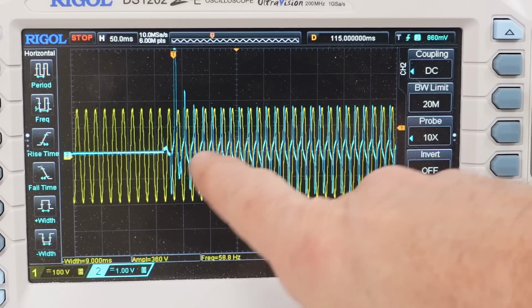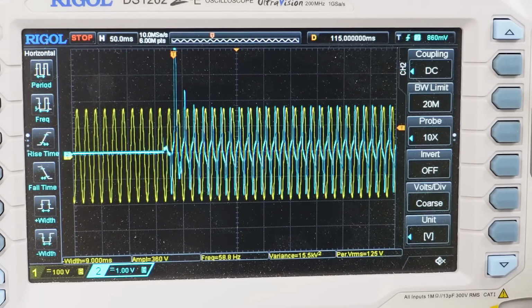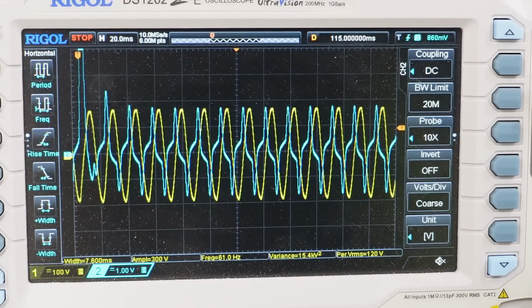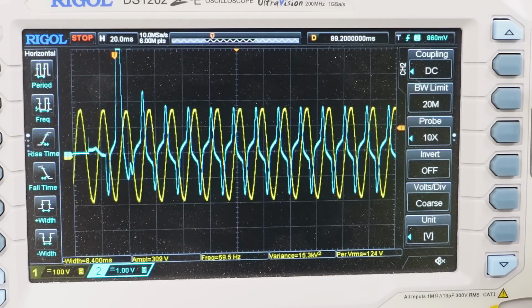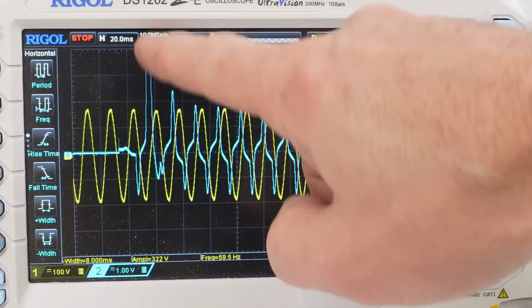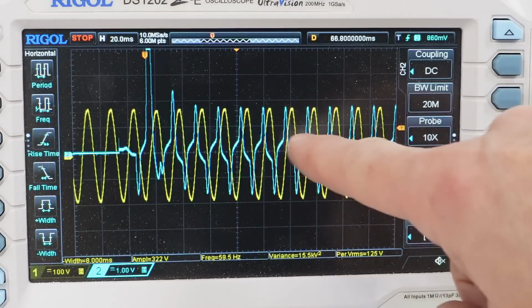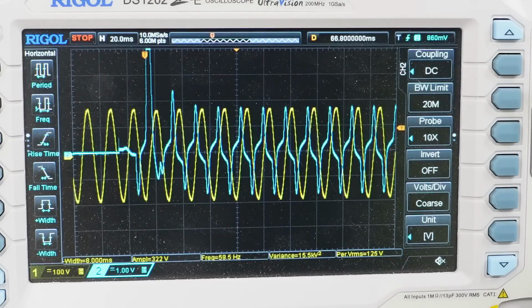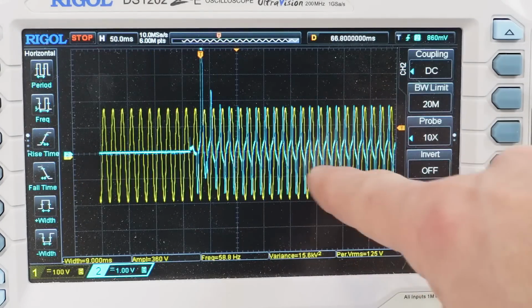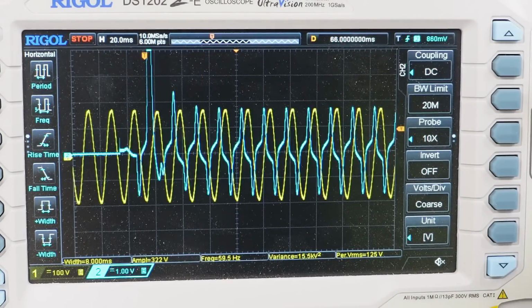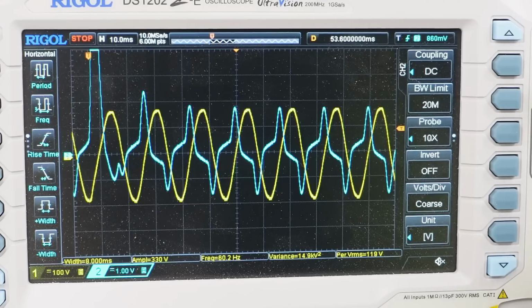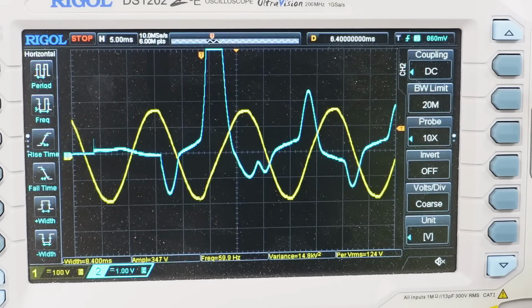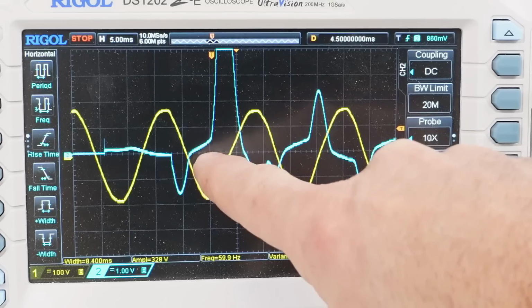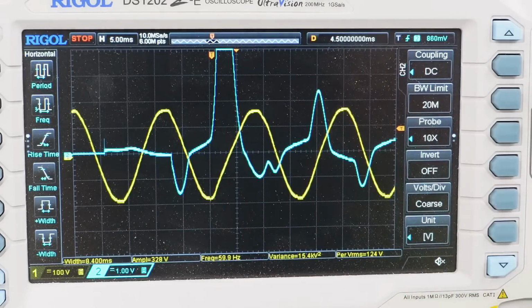Yellow trace is voltage, blue trace is current at 1 ampere per division. You can see it spikes quite a bit initially, but then settles down within a few cycles. So that wouldn't account for the hum we hear at the start. That spike is because the transformer started at a slightly unfortunate phase in the voltage, so its magnetic field got out of balance.